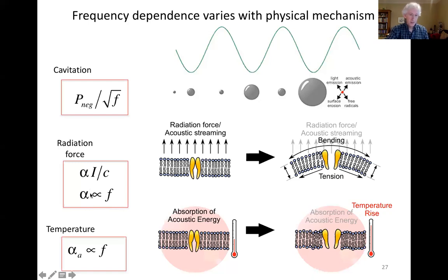Because the attenuation coefficient will go up with acoustic frequency, radiation force will increase with higher frequency, cavitation will decrease. Temperature also will increase because the absorption will increase with acoustic frequency. So acoustic frequency won't really distinguish between radiation force and temperature, but it will distinguish between cavitation and radiation force and temperature.